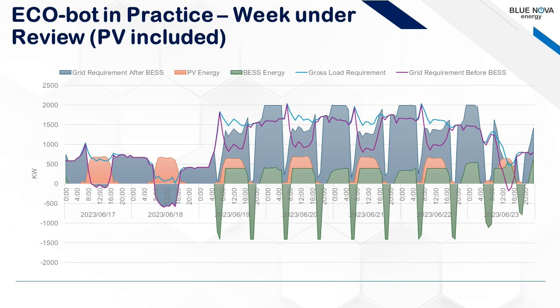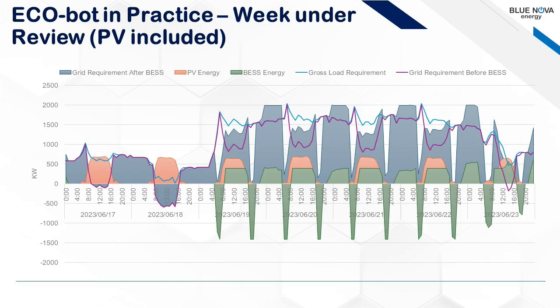And the reason for that is that the annual demand charges are depending on this peak here. So we do not increase the maximum demand of the plant. Here in orange, you can see the PV coming in on a daily basis. And then here you can see the reduction, which is the grid requirement. Sorry, this is the grid requirement before the BESS, and this is the grid requirement, this one here, after the battery storage system.